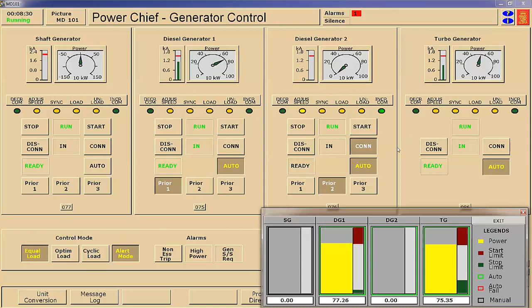Alert mode tells the power management system not to take any generators off the line. In other words, on this same diagram, if the load was to drop down into the green on these generators, that's its low load point, it would normally take one of these 3 generators off. It won't do that in this case because you have instructed it not to. And as part of the chief engineer's standing orders, he wants all 3 generators to be in service during the entire maneuvering mode.